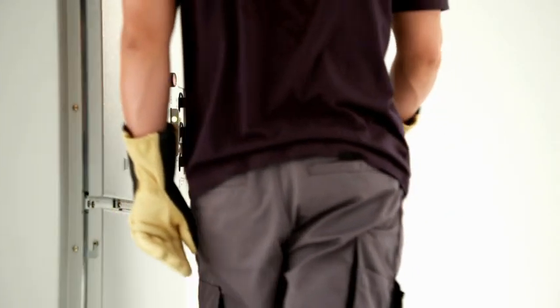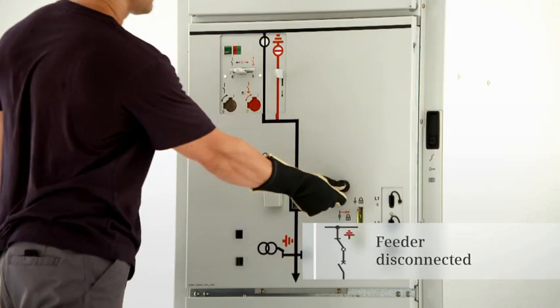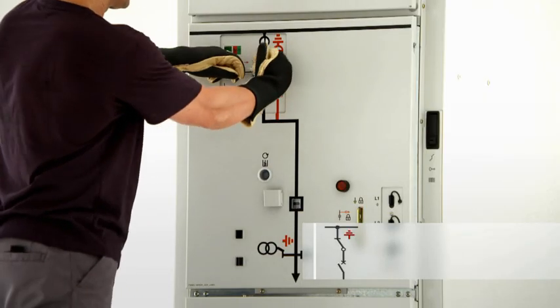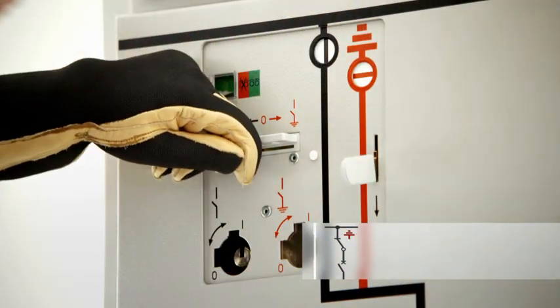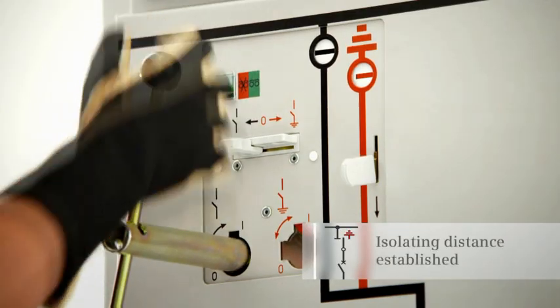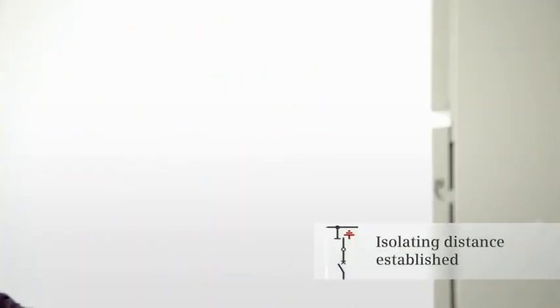To disconnect a feeder from the bus bar and to earth it subsequently, the circuit breaker is first switched to the open position. Only after the interlock lever has been pushed down and the control gate has been pushed to the left can the three position disconnector be switched to the open position by turning the operating lever counter-clockwise.